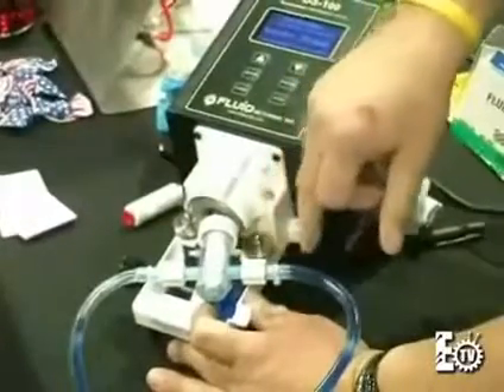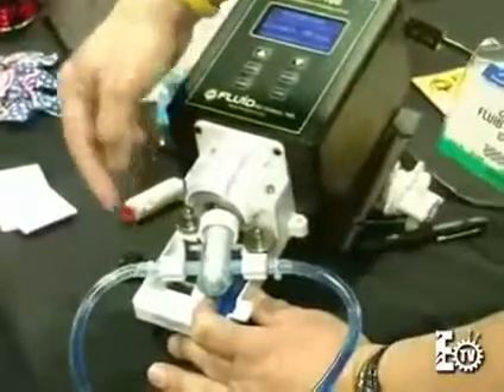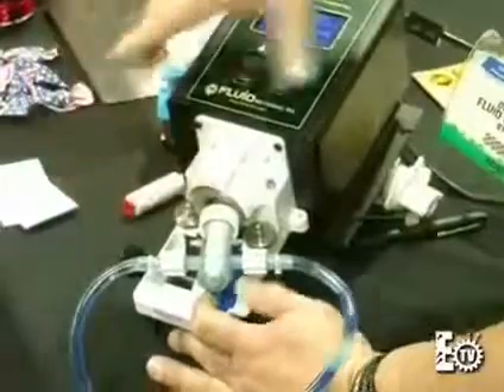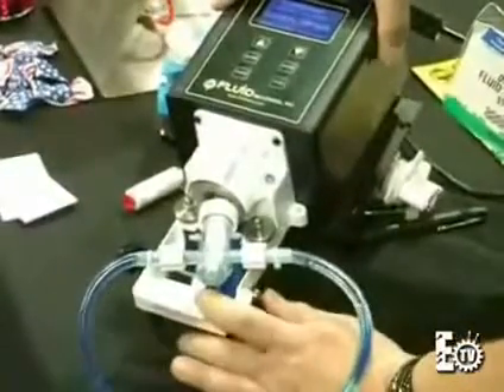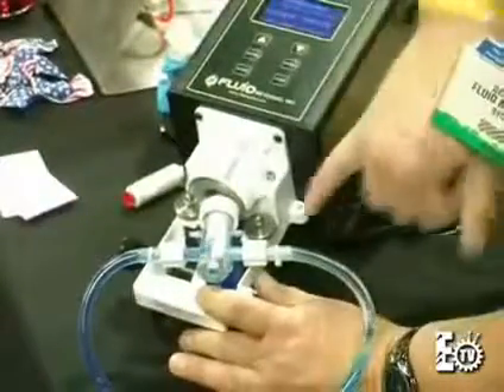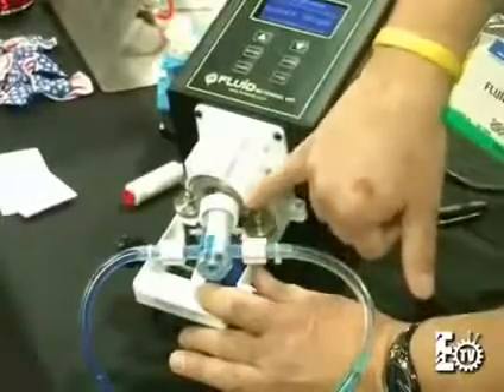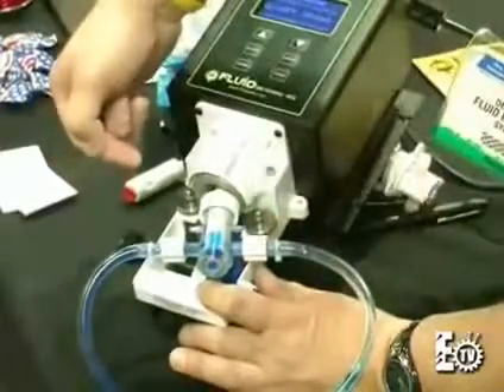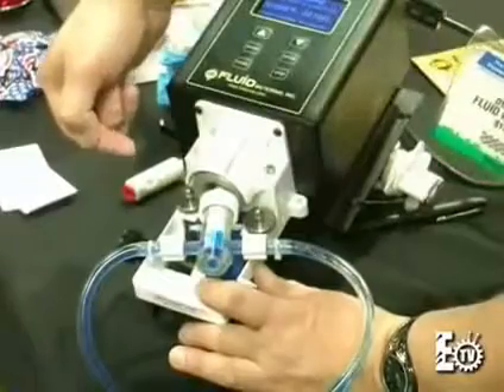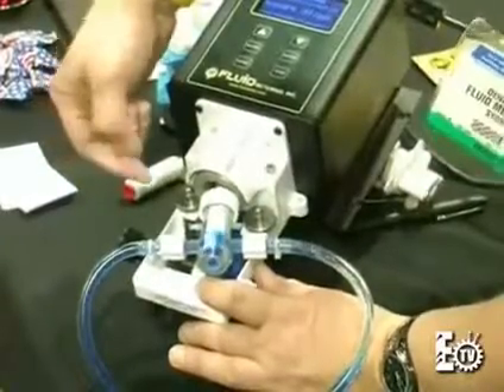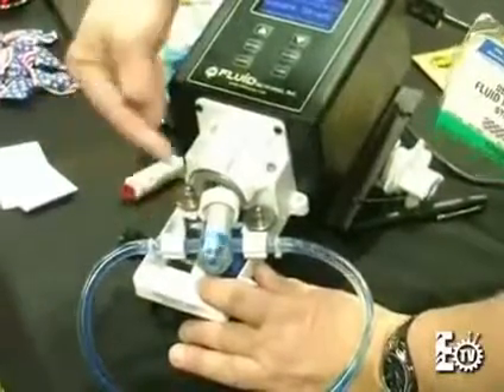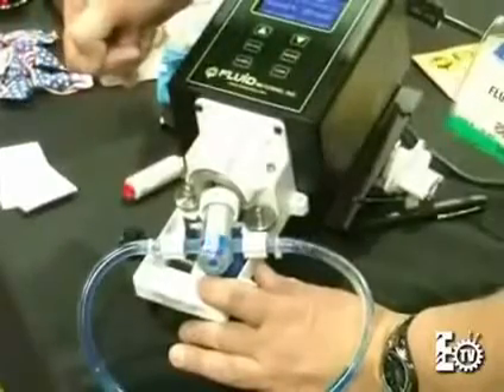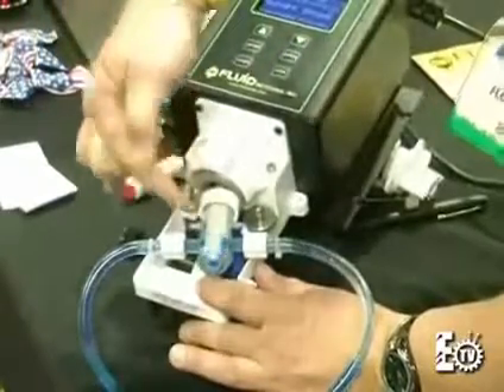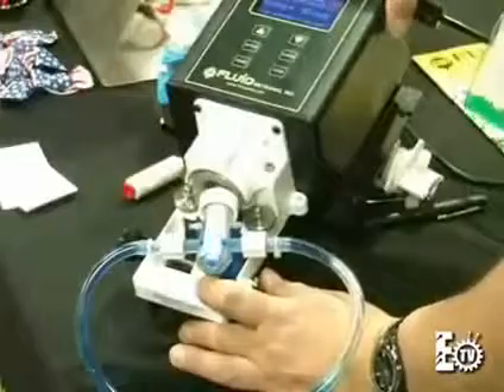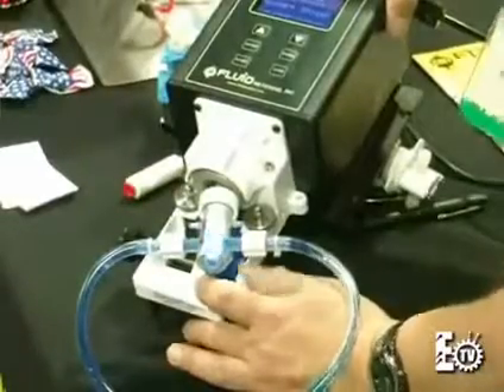You'll notice there's a flat at the very bottom of the piston. That's what's alternately opening and closing your two stationary ports. By going extremely to one side like so, the piston is rotating up. That's when we self-prime. We'll lift 15 feet of fluid or gas, sealing it, simultaneously opening up the other side. Now, on the downstroke, we discharge, where positive displacement will go up to 100 psi.